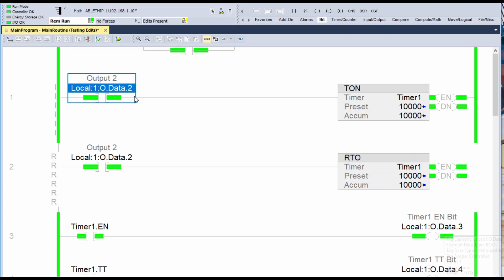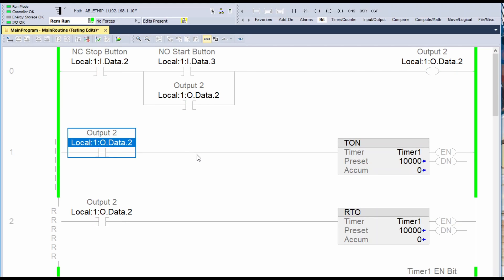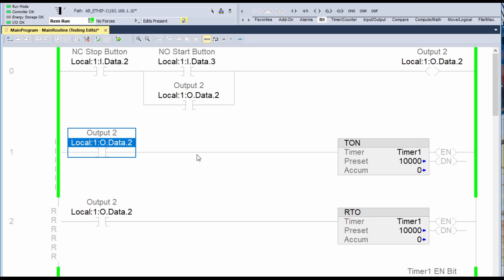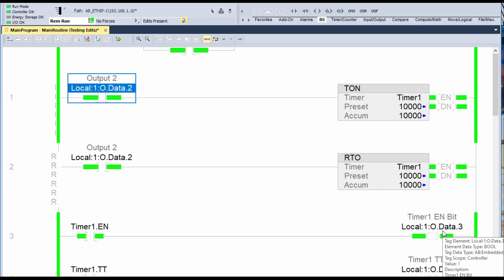Our enable value is still true and the done bit has now set. Let's reset this program and see if we can verify the behavior. I'm going to hit the stop push button — and yes, it is working as an on delay timer. As soon as I hit the stop push button, the timer accumulated value went to zero. So it's no longer working as an RTO. With the on delay timer, if I turn on the start it accumulates, but if I stop it at any point, the value goes back to zero. We can see the enable and TT bits are true as the accumulated value goes up, and once the accumulated value equals the preset, the done bit sets.